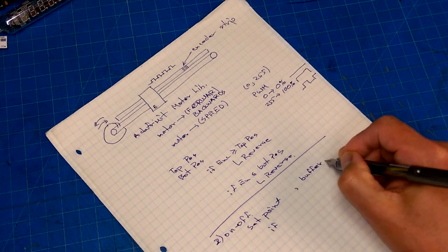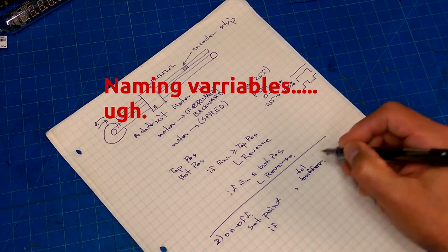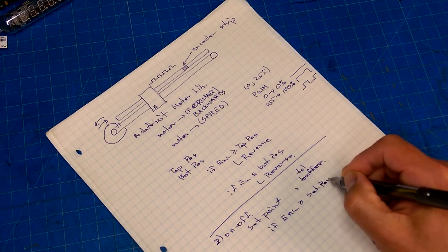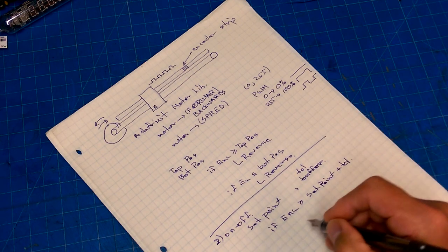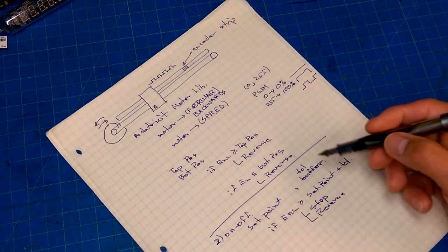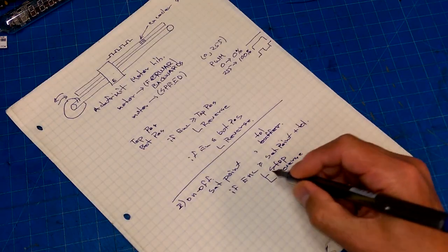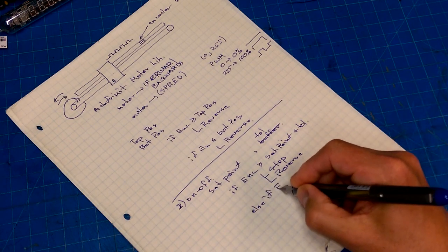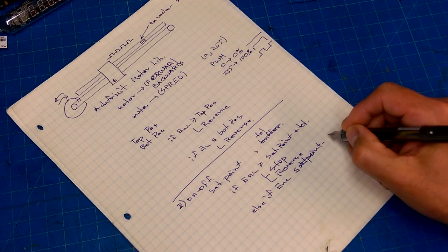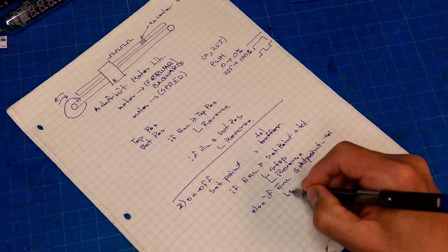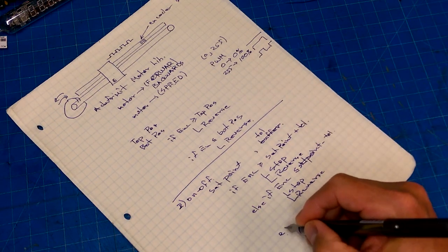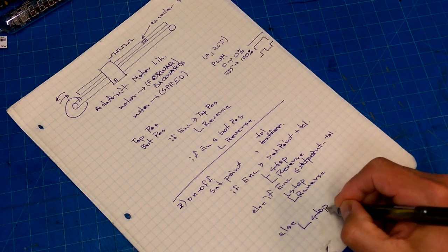So, if the encoder is bigger than or equal to set point plus a tolerance, then we're going to stop the motor and then we're going to reverse it. Else, the encoder is less than or equal to set point minus our tolerance. Then, again, stop, reverse. And if we happen to fall into this tolerance band then we are going to just stop the motor.